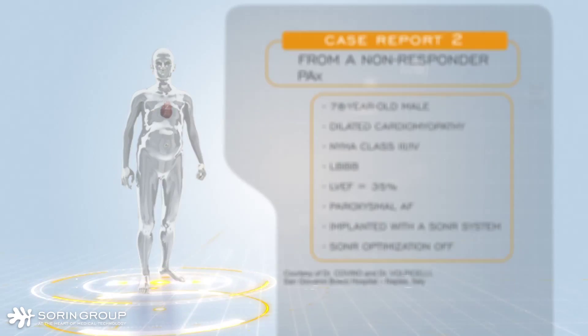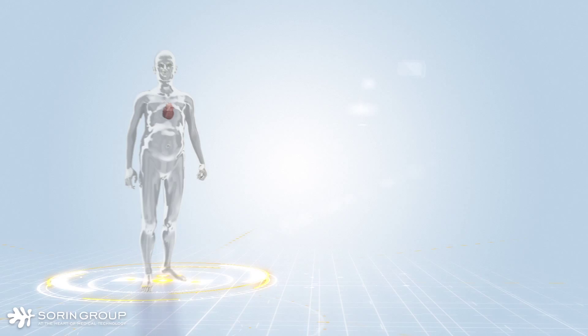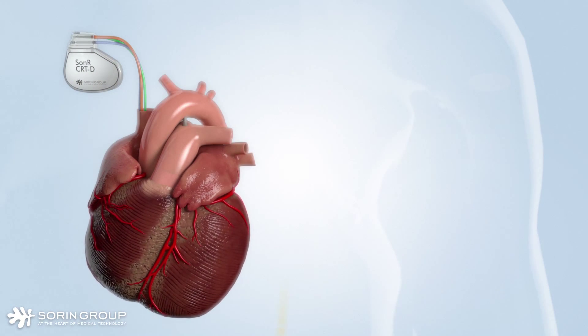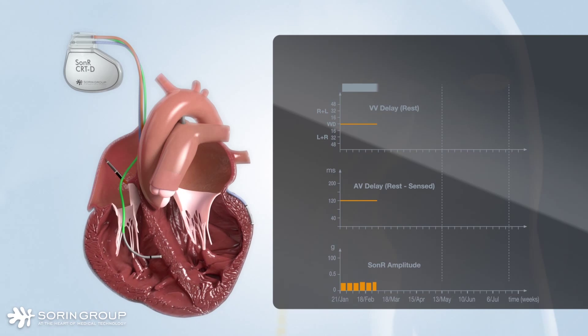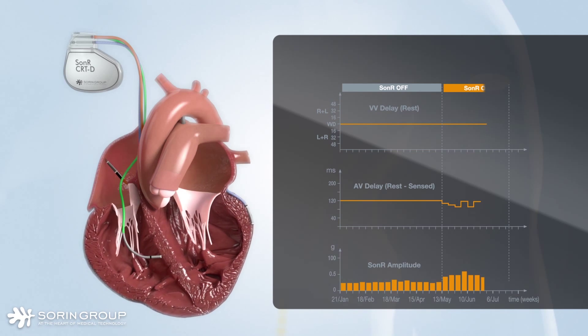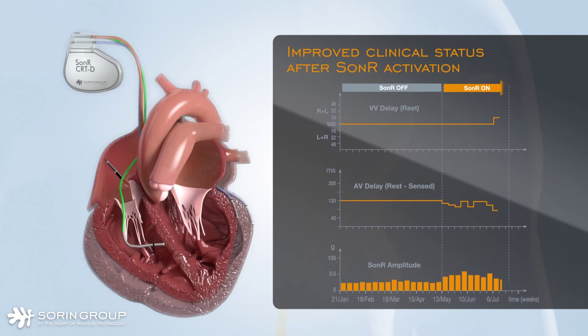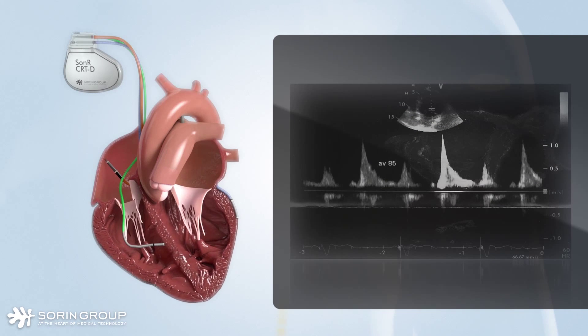The second case report illustrates how a non-responder patient was turned into a responder after SonR activation. The patient was implanted with a SonR system, but SonR was in monitoring mode only without automatic delay settings, and the patient did not improve during that time. Five months after implant, SonR automatic settings were turned on. The AV and VV delays were automatically adjusted and SonR amplitude immediately increased significantly. At the seven-month follow-up, the patient's clinical status showed dramatic improvement, with a 59% left ventricular ejection fraction and NYHA class 2. SonR automatic settings were confirmed by echocardiography and ventricular filling time was shown to be optimal.